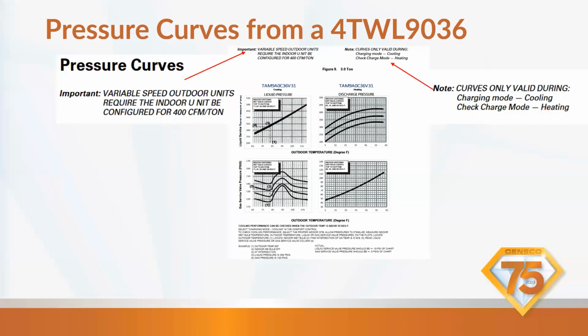Check charge mode heating is going to run that compressor at optimal speeds for the environment it's in. It's calculating outdoor temperature, indoor temperature, humidity, compressor speed, whatnot. So it's not necessarily running that compressor at 100%. That's why you got to be in check charge mode heating below 55, charging mode cooling above 55-degree outside temperature. Because you won't get a correct charge if you're just bumping that compressor up to 100%, like in traditional single stage equipment, because single stage equipment is just 100%.